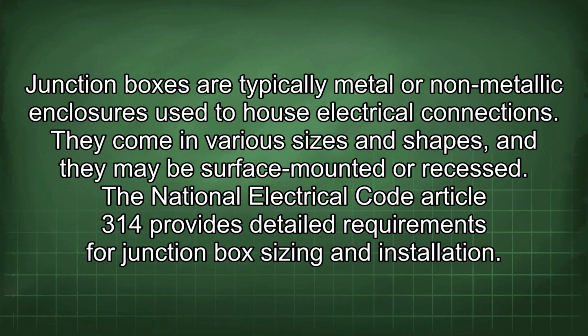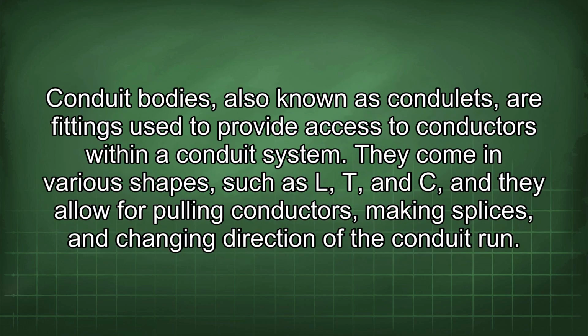Junction boxes are typically metal or non-metallic enclosures used to house electrical connections. They come in various sizes and shapes, and they may be surface-mounted or recessed. The National Electrical Code Article 314 provides detailed requirements for junction box sizing and installation. Conduit bodies, also known as condulets, are fittings used to provide access to conductors within a conduit system. They come in various shapes such as L, T, and C, and they allow for pulling conductors, making splices, and changing direction of the conduit run.